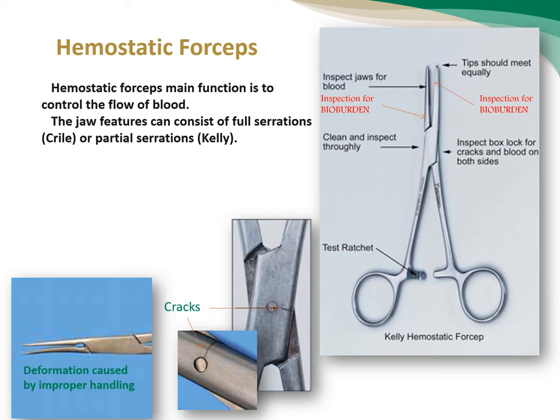We have to check for cracks in the box lock, and that the straightening of the jaws is not deformed, like we see in the bottom of the picture here. Also the cracks are seen here in the box lock. Also check for any bioburden remains after the cleaning in the jaws and the serration. Also test whether the ratchet functions okay or not. That's what about hemostatic forceps.